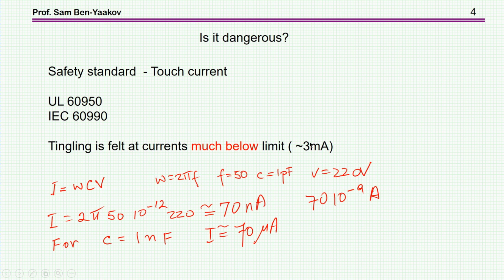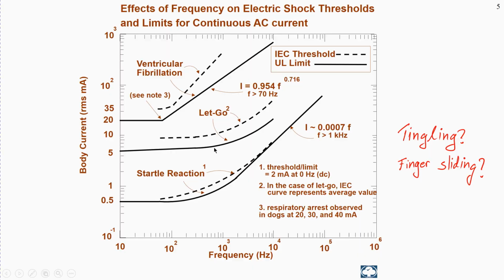So these currents are way below the 3 milliamp limit, so let's not worry about danger here. In fact, if we look at the standards—this is the IEC threshold and UL limits, the solid and broken lines—they talk about a startle reaction. That is, as you touch something, you pull your hand back, feeling a tingle.